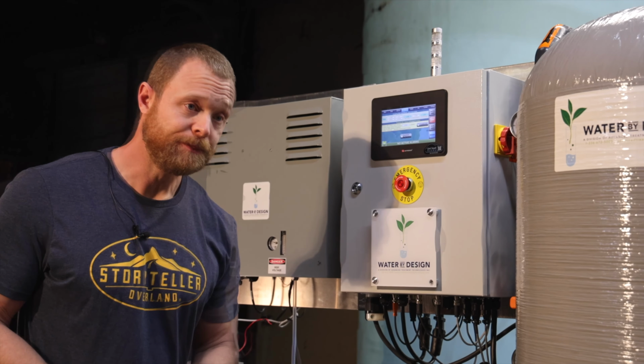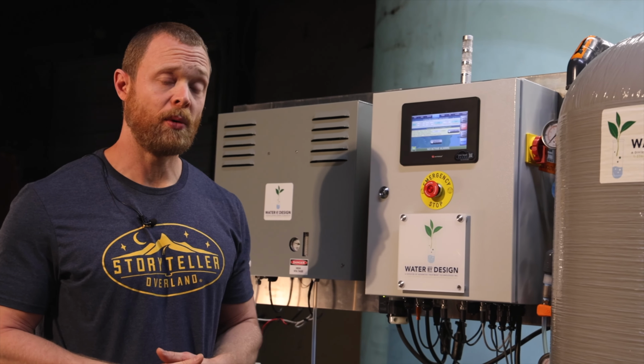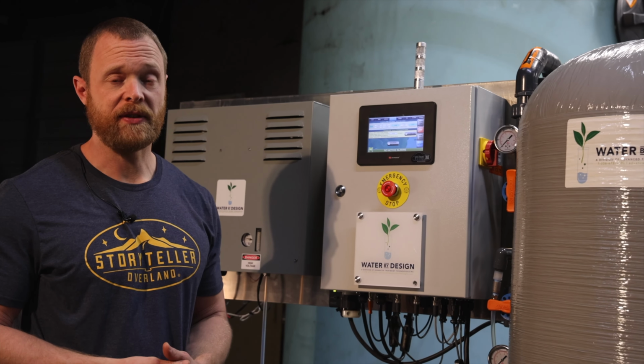We recommend that you calibrate your probe about once a quarter. That's probably a little more frequently than most people do, but it's a good general recommendation. And again, it just takes about 5 minutes. So we would recommend that you do that about once a quarter. If you do that, everything will be fine with your calibration.